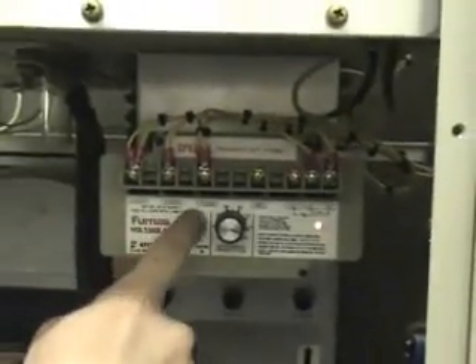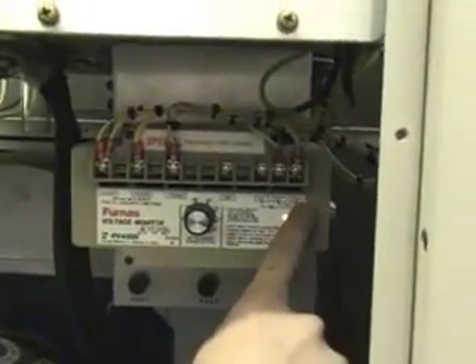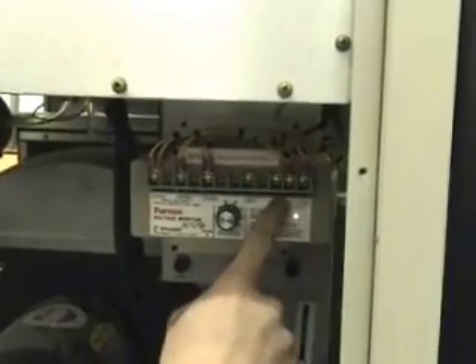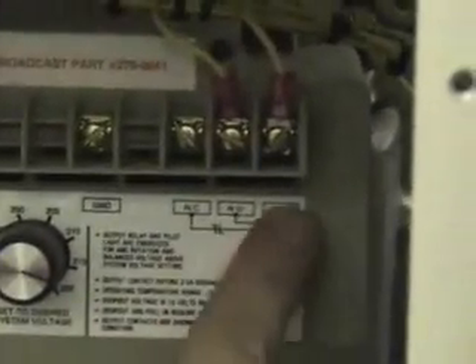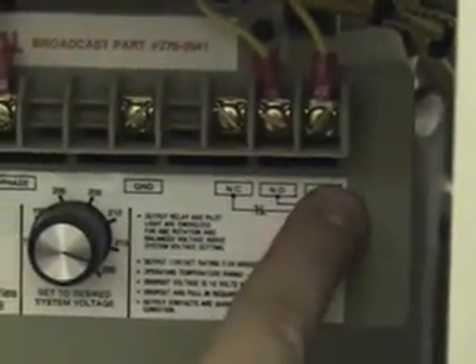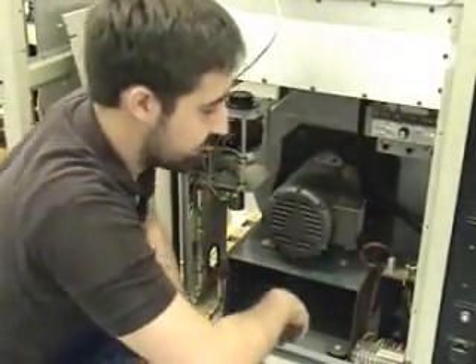You've got phases A, B, C, or 1, 2, 3, and a relay. It'll be common and normally open. The relay is going to run, complete the circuit that turns the voltage on for the control cabinet. So if this isn't working or your phases are out of order, the transmitter won't come up at all. So you want to look at here in the beginning. Make sure the breaker is on here for the screen and all the breakers here. Make sure they're all in.